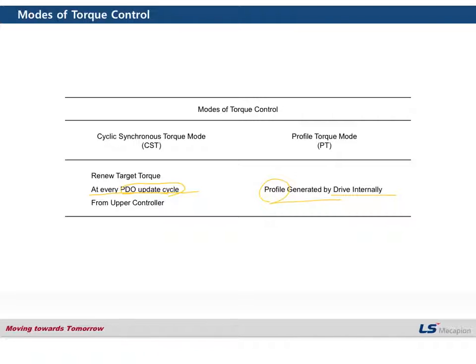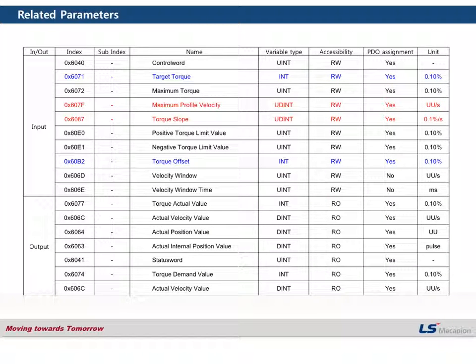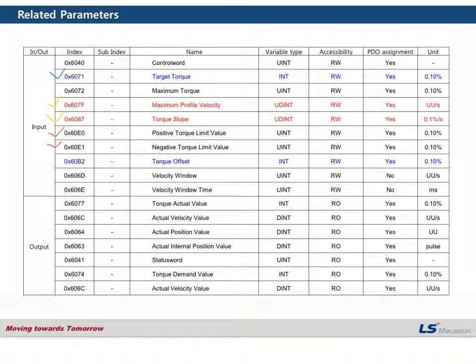The related parameters with torque control are like this. These two parameters are only for profile torque mode. The positive torque limit value and the negative torque limit value — this torque limit function allows the user to set different values between forward operation and backward operation. We can use this function for some kinds of tension machines. Today I'd like to show you one example that uses the target torque and the torque offset.